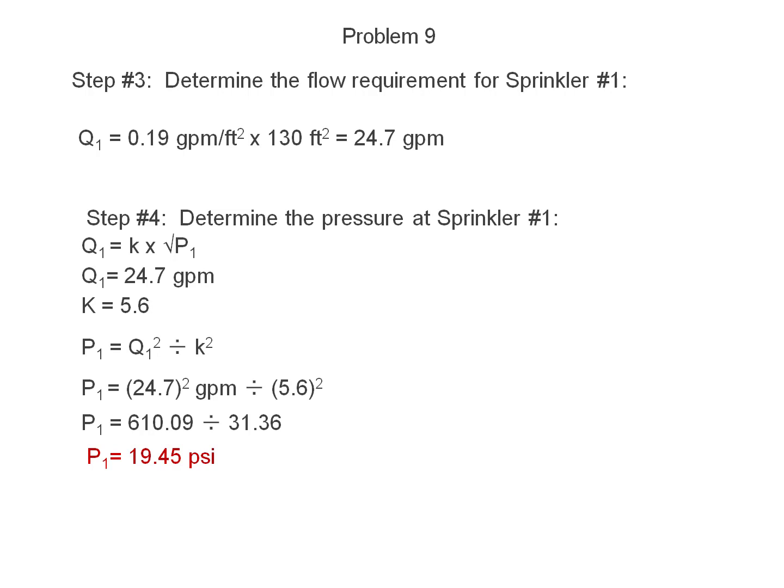Next, determine the pressure at sprinkler number 1. Q1 is equal to K times the square root of P. Q1 is equal to 24.7 gallons per minute. K factor is equal to 5.6. P1 is equal to Q1 squared divided by K squared. P1 is equal to 24.7 squared divided by the K factor of 5.6 squared. P1 is equal to 610.09 divided by 31.36. P1 is equal to 19.45 PSI.